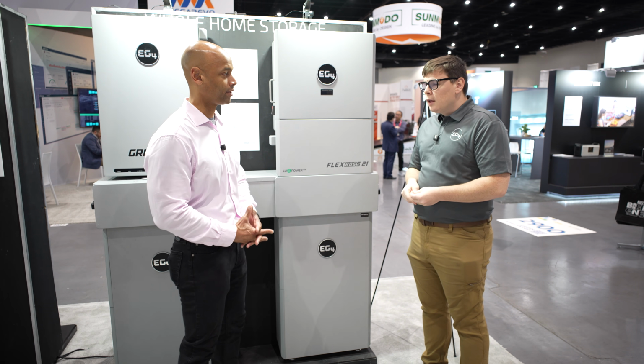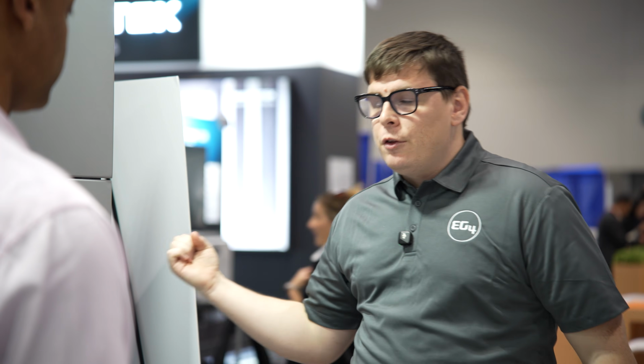When we went on job sites with our 18K installers and looked at other 200 amp solutions around the industry, they were using a 200 amp manual transfer switch because you have to be able to replace the inverter without interrupting power to the customer. Then they were using a 200 amp overcurrent knife switch on the input side, plus 3-aught wire and EMT conduit. By the time they left the wire store to do the job, they had spent $2,000 on transfer switches, disconnects, and wire. So there's a lot of money there we felt we could do much better with.